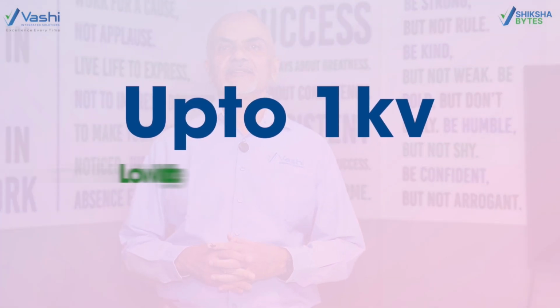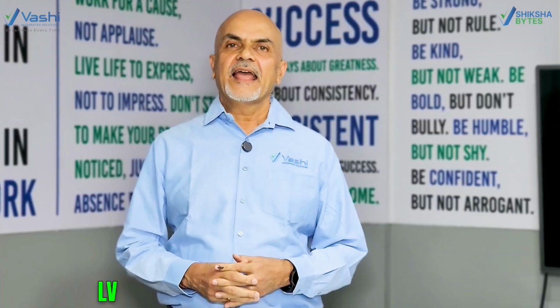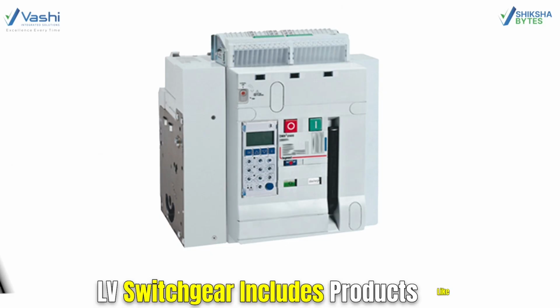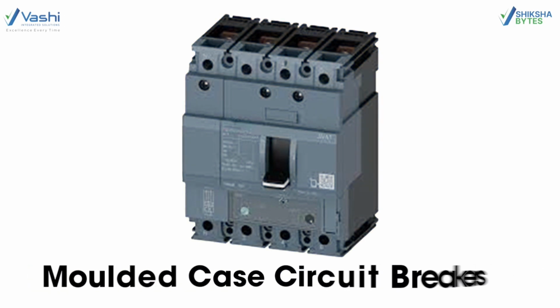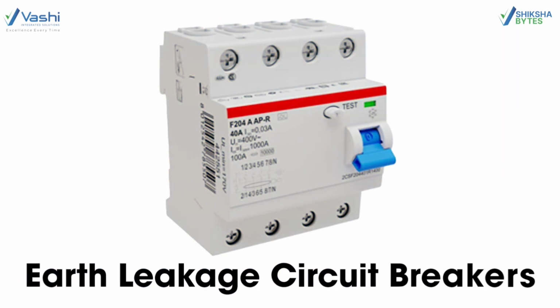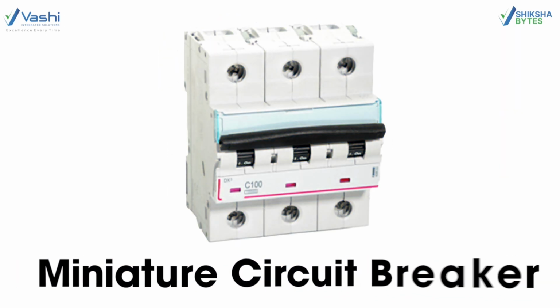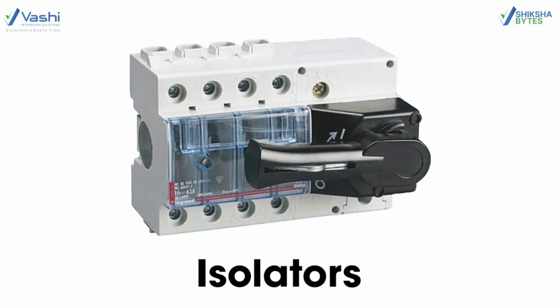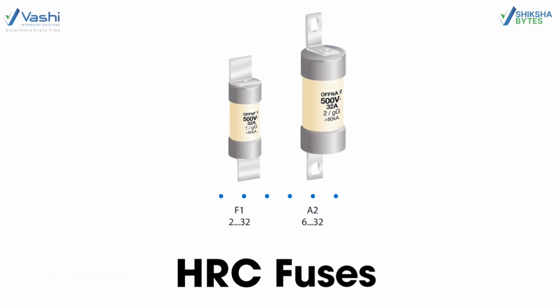Electrical switchgear rated up to 1 kV is known as low voltage switchgear, or LV switchgear. LV switchgear includes products like air circuit breakers, molded case circuit breakers, earth leakage circuit breakers (also known as RCCBs), MCBs (miniature circuit breakers), isolators, switches, as well as HRC fuses.